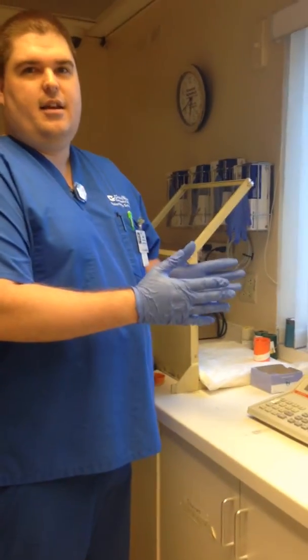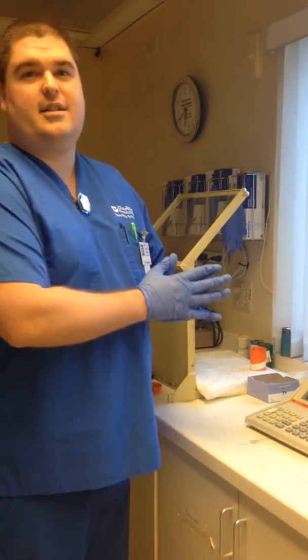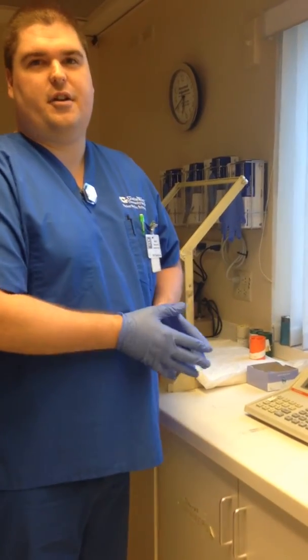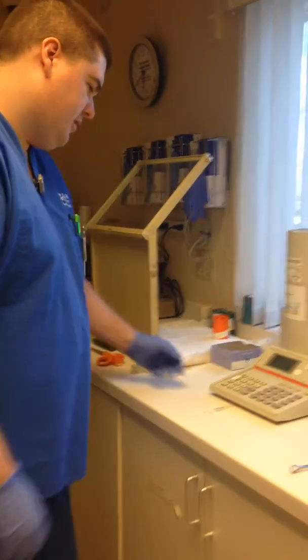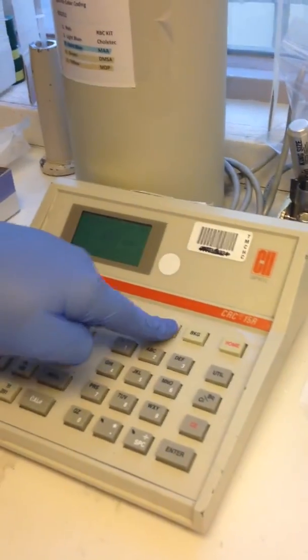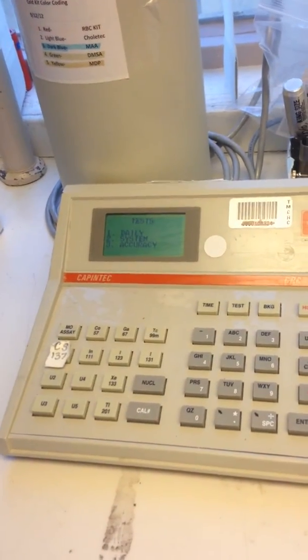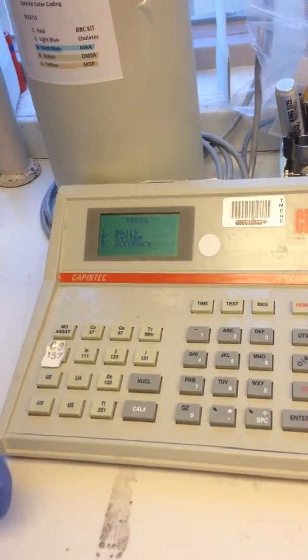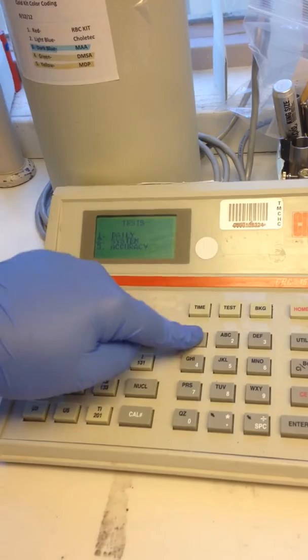And so when we say constancy, we want to make sure that throughout the day it's consistent, that we're consistently getting our accurate readings, okay? So if you want to look right here, you're just going to push test, and it'll come up with different tests. And we want to do our daily test, which is, we would push number one, so I'll push one.